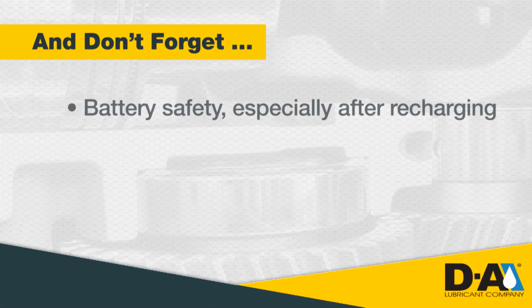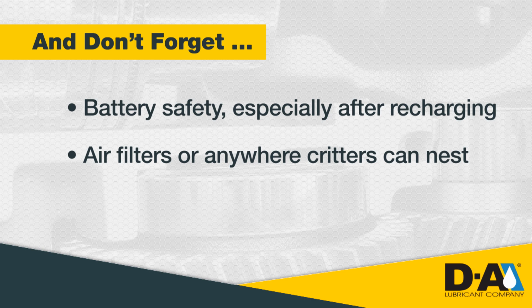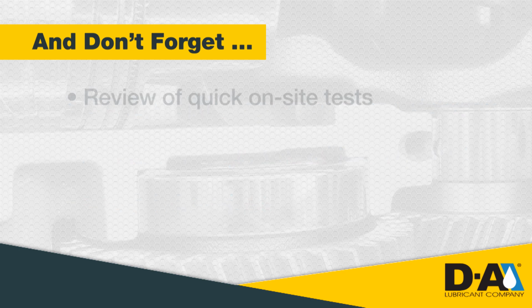And don't forget, battery safety, especially after recharging said battery, for fear of poisonous and or explosive fumes. Air filters or anywhere critters can nest, or wind, as Nick indicated earlier, that can accumulate debris. Special oil analysis protocol for recommissioning of idle equipment. Review of quick on-site tests. A maintenance person on site could do a simple visual inspection and something as elementary as a hot plate test to determine moisture content of any given lubricant.